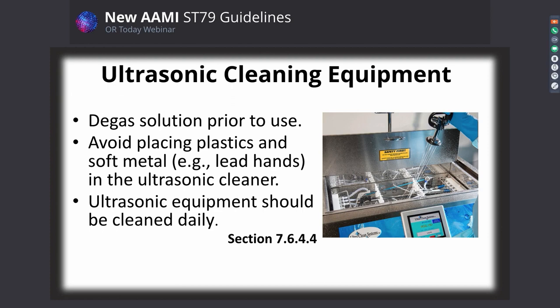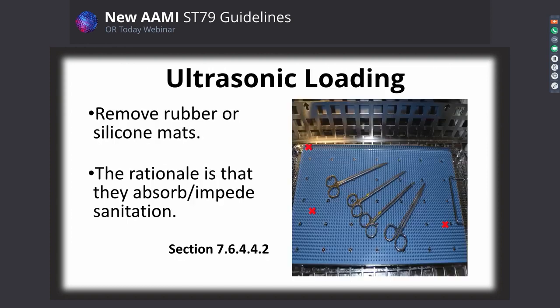Ultrasonic cleaning should be cleaned daily. So I kind of covered that in the previous slide. Remove rubber or silicone mats. It's been proven that these mats can actually inhibit ultrasonic cavitation. And maybe you might expect that because it's going to absorb some of this energy because of its elasticity. The rationale is that they absorb and impede, thus sanitation is the way the AAMI document states it.